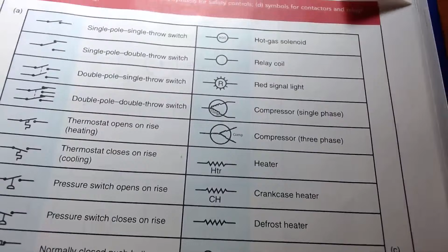You have your hot gas solenoid up here on the top right. You're going to have those on certain style package units. Reheats, relay coil, your red light signal. If you're not sure what the red light signal is, that's the red light that comes on your thermostat, or if you have an indicator light on your system.